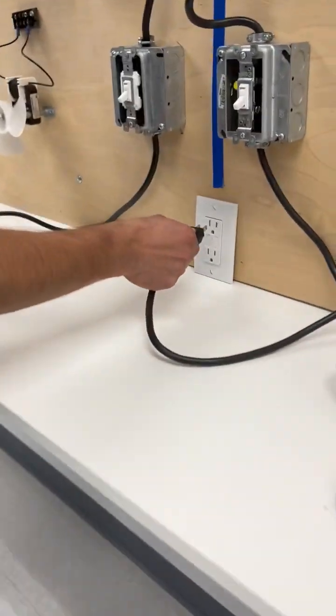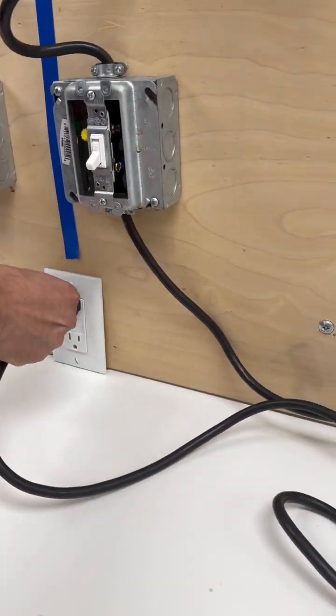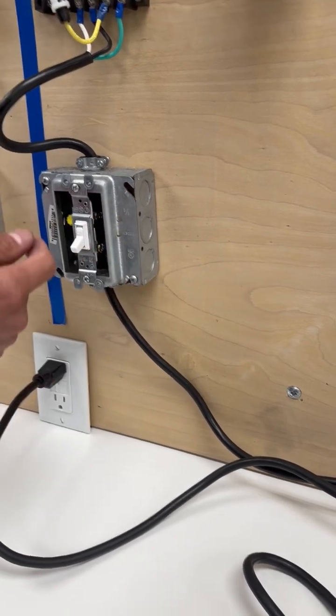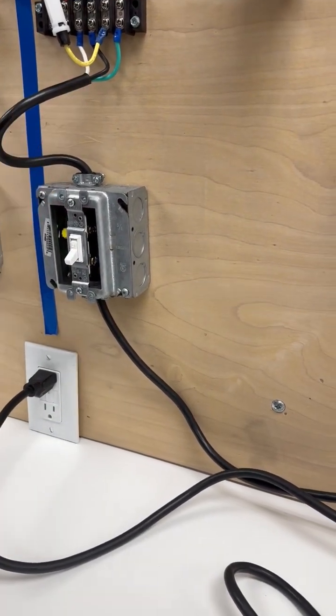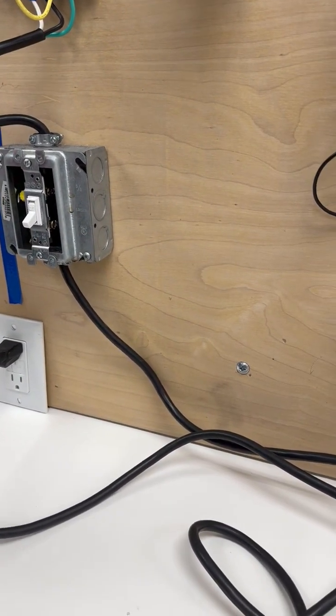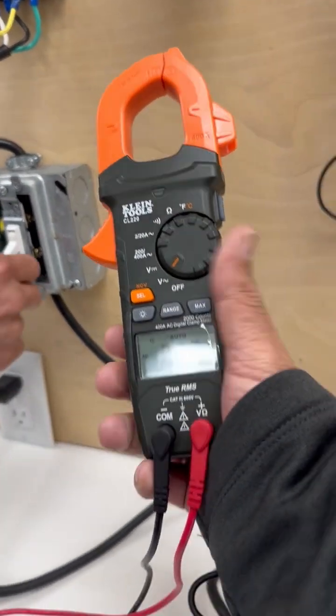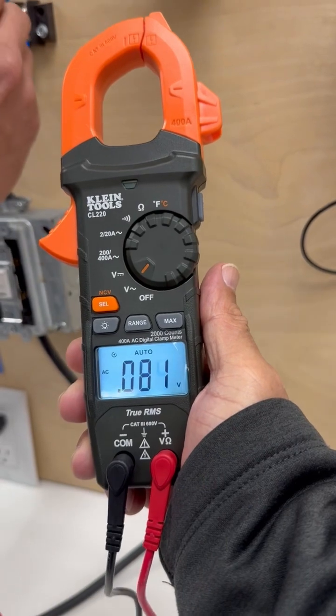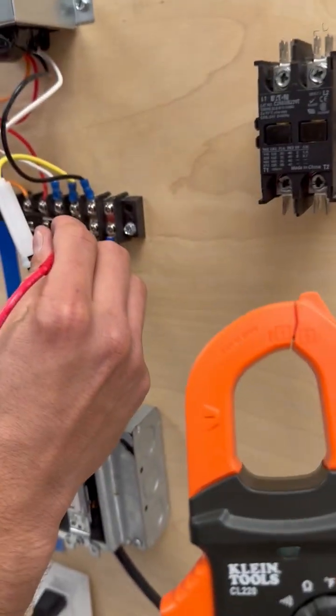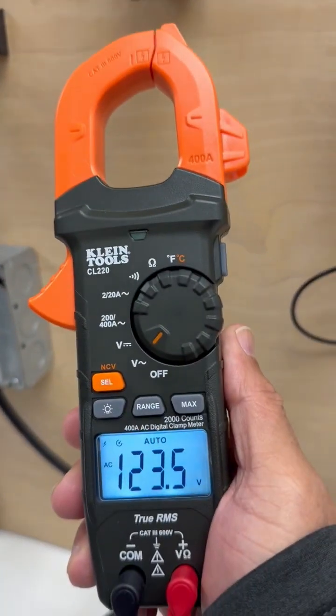So we're gonna start by connecting our 120-volt pigtail. And this is our 1900 box with a single pole switch supplying 120 volts into the terminal strip. So we're gonna measure the incoming power from line to neutral. We got 120 volts coming in.